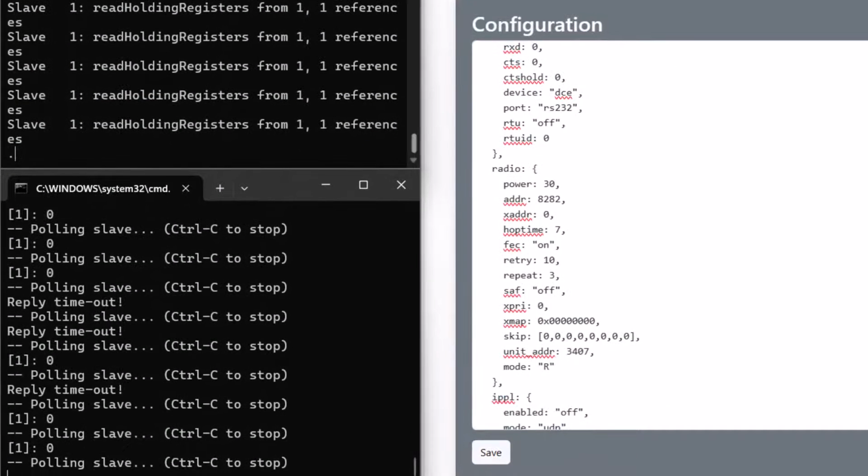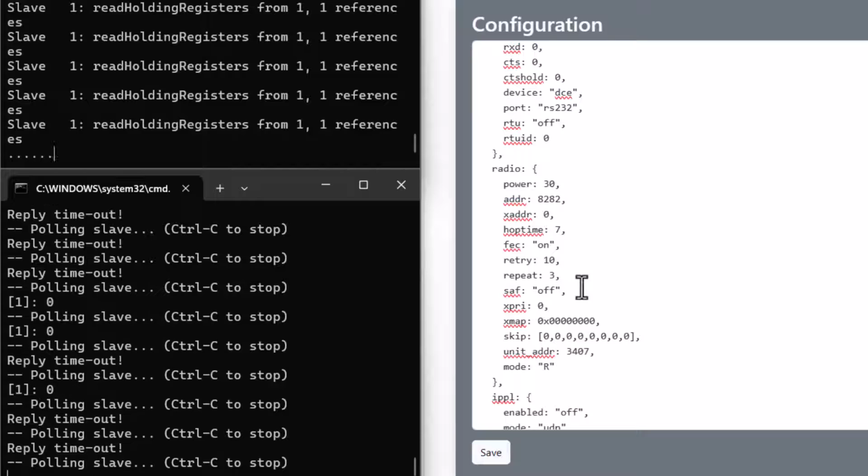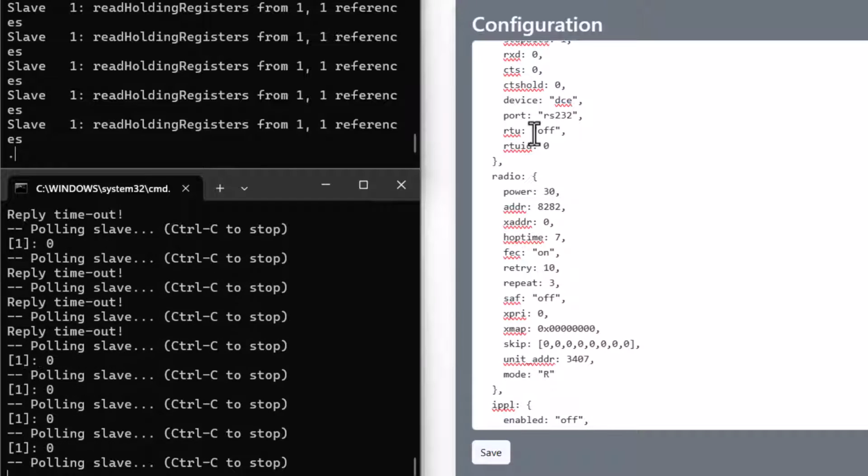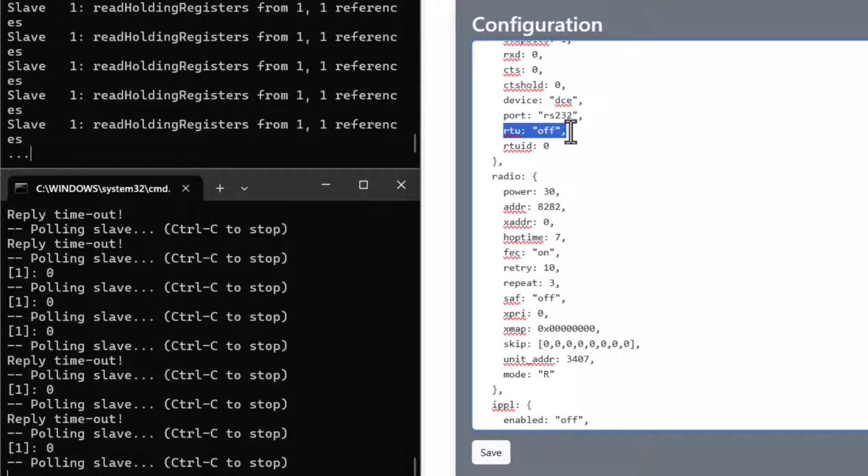One thing I've read in the manual is this RTU on-off. This actually refers to the GE RTU simulator software. So this isn't anything to do with the actual Modbus RTU protocol, but instead, if you're using their polling simulator, this is where you would enable that. And then I would assume this is the RTU ID for that as well.